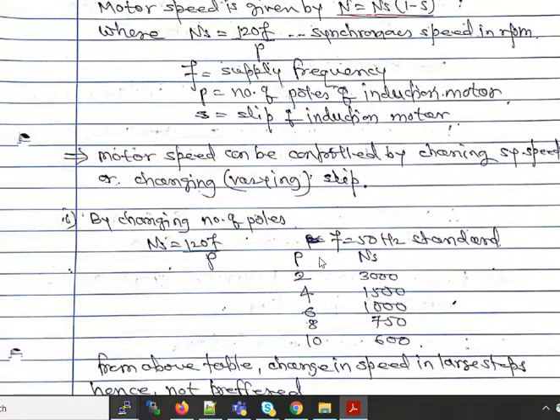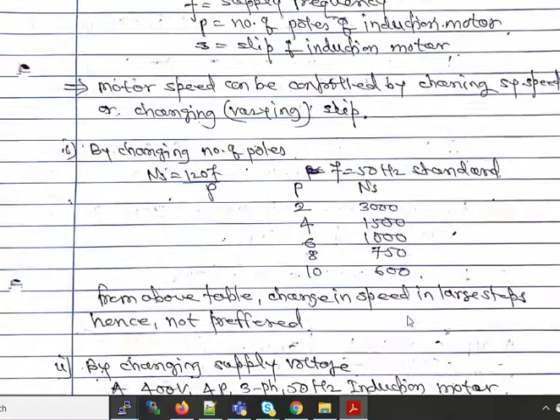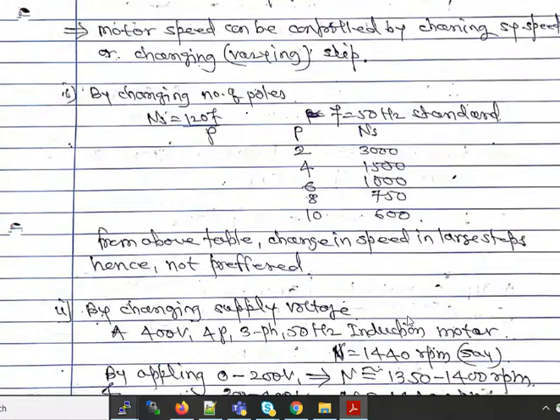By increasing the number of poles the speed decreases, but the decrease in speed occurs in large steps — 3000 to 1500, then 1500 to 1000, 1000 to 750, and so on. Therefore the change in speed is large in steps and hence this method is not preferred.